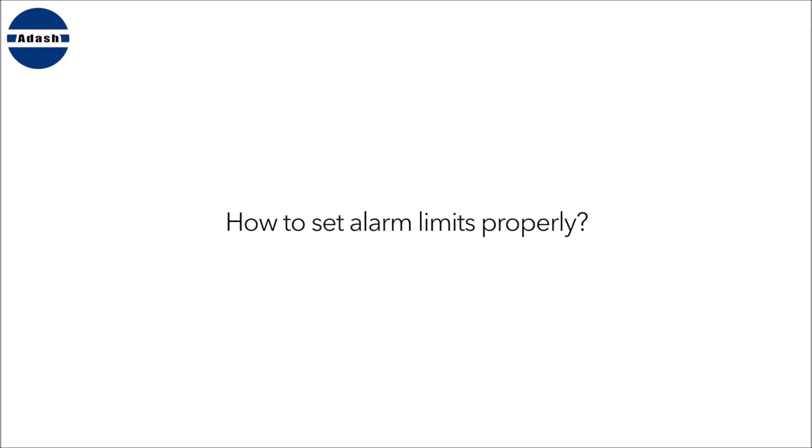It is very difficult to use any standards because of the above reasons. You should think about each individual machine, what vibration level is optimal for it. Setting of limits by statistics is the tool for how to set reasonable alarm limits.